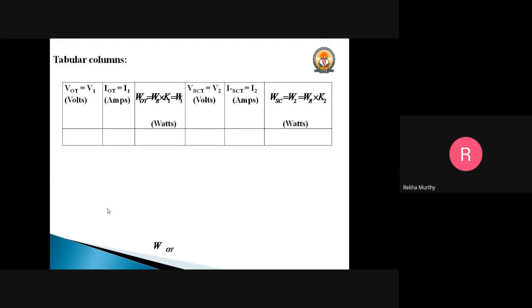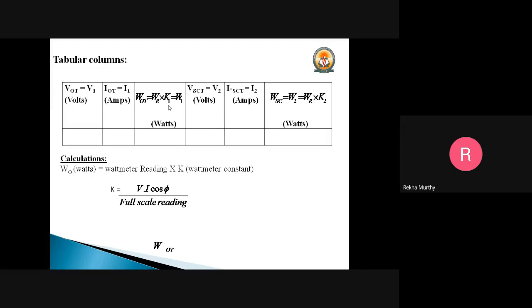The tabular column will record the voltage at the first transformer (V0T), the no-load current (I0T), and the first wattmeter reading. We need to calculate k1 and k2 constants and multiply them with the watt readings to obtain actual power. The short circuit voltage at the secondary part of the circuit and the current, which is kept constant at 8.7 amperes, are also noted.